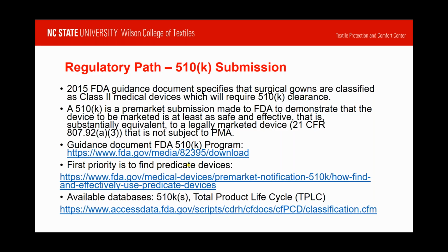All right, so first of all, you have to identify that, and then you have to do a series of tests in order to demonstrate that, yes, the functionality that you're claiming is equivalent to that of the predicate device already on the market. To be honest with you, that's not a difficult thing to do, but you are required to do the testing yourself and present the data to the FDA. The FDA doesn't do the testing. You go to an independent testing house or wherever you need to go to demonstrate that you have done this test and that the results are reliable and reproducible.